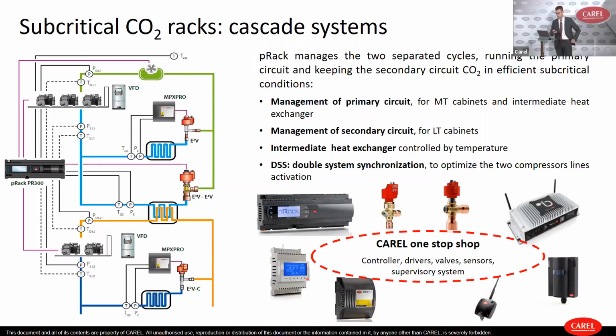From the pRack point of view, in subcritical CO2 racks like Cascade, we can manage, of course, the primary circuit with the compression lines and gas cooler, or condenser in this case, the secondary part of the circuit with the compression line, and of course the intermediate heat exchanger that we use to keep the CO2 in the secondary circuit always in subcritical conditions.